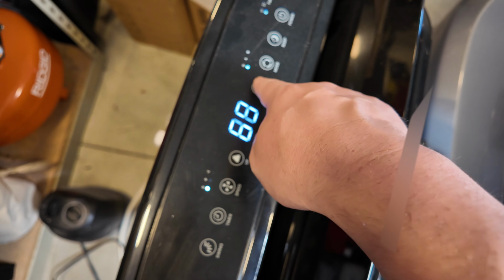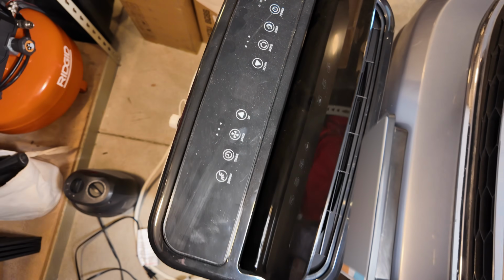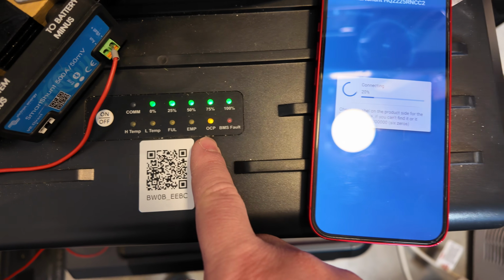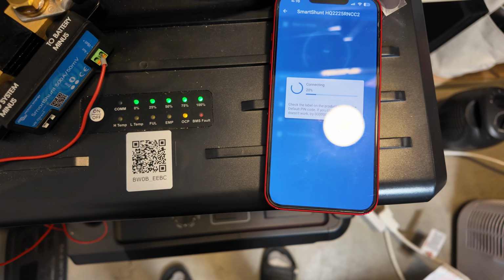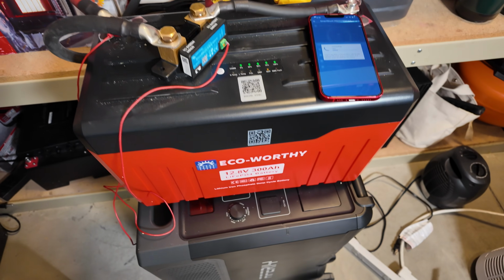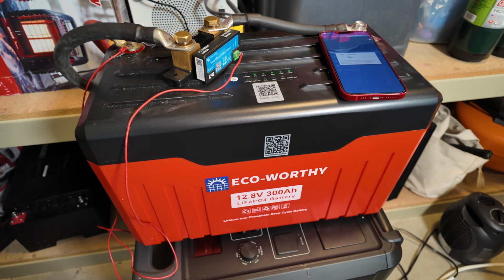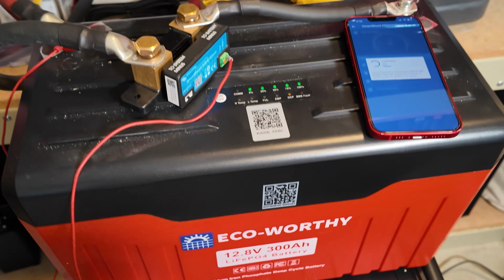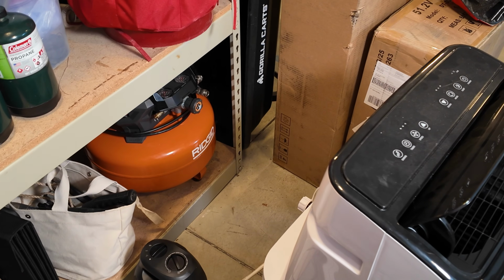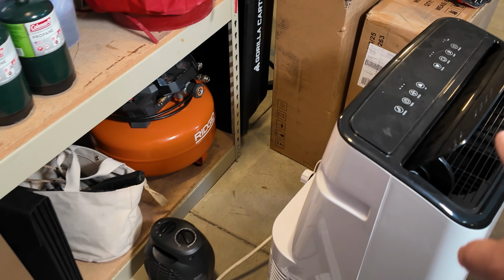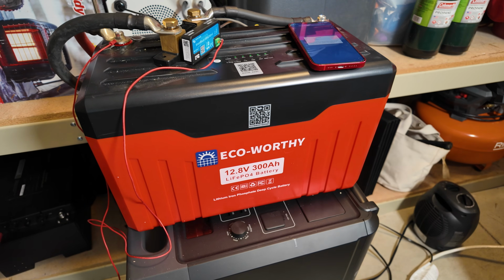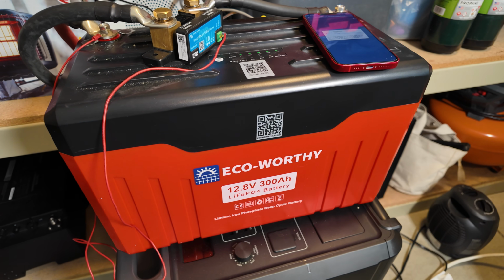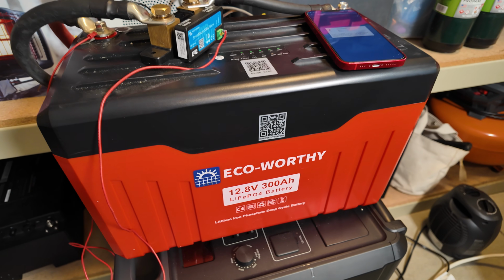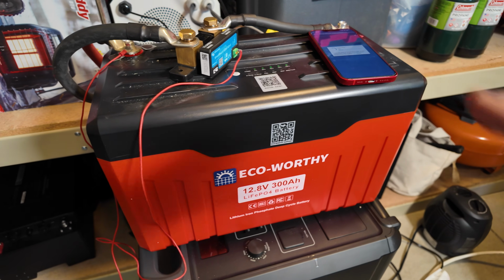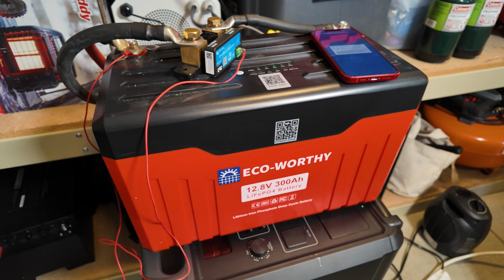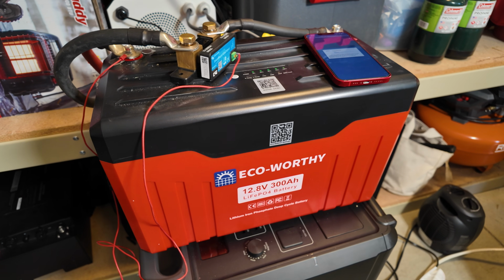Here we go. Nope, too heavy of a surge. Once again we've lost it here on this connection, so that's actually good to see from a safety perspective. This has very quick acting overcurrent protection. Could be a bit of an issue if you're trying to start, say, a 15,000 BTU RV air conditioner, because that's kind of equivalent to what this is, it has no soft start or anything. But all the recent batteries from EcoWorthy that I've tested have been very focused on safety. I'd personally rather have them err on the side of safety than compromise it to potentially run a heavier load that it probably shouldn't be doing by itself.